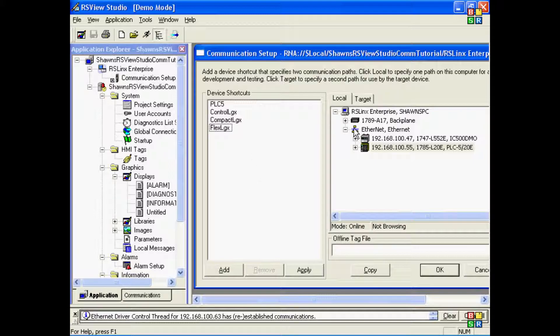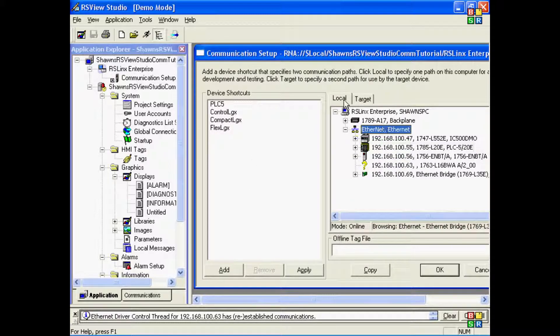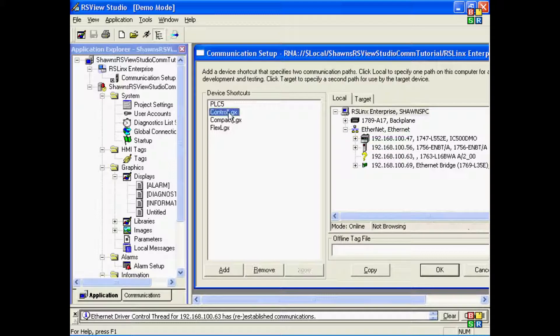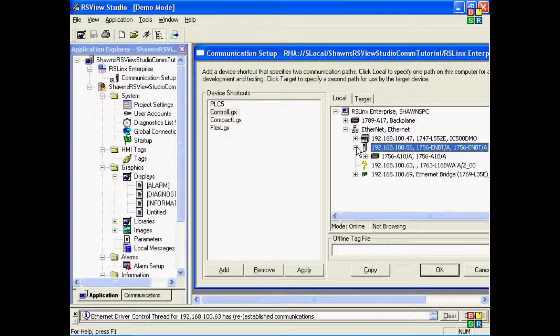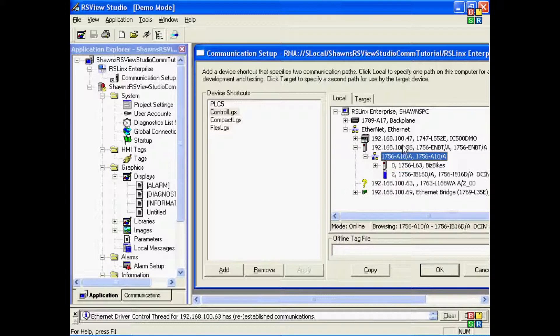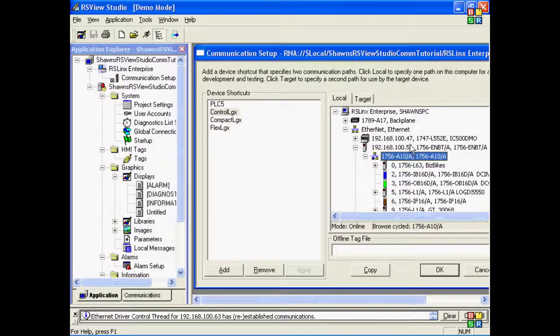Okay, now I'll go ahead and click on my Ethernet driver and let my local tab Ethernet driver browse for the PLCs. In this case, you can see for the ControlLogix, it'll be sitting in a 1756 chassis, and I'll access it through a 1756-ENBT Ethernet card. So I'll expand the card, expand the backplane chassis, and then I'll see all the devices in that chassis.